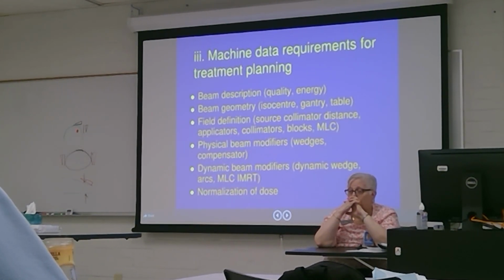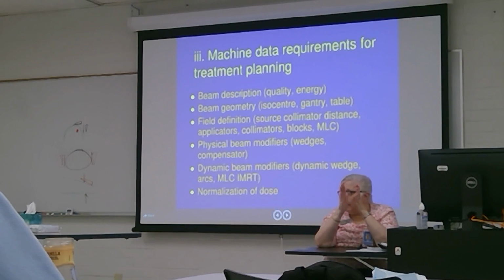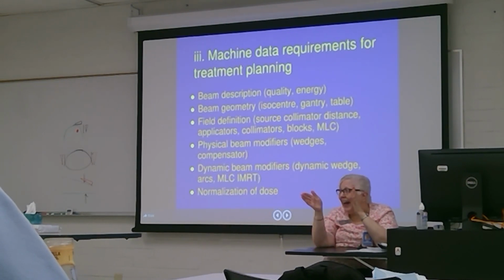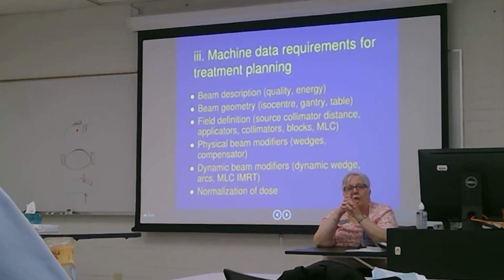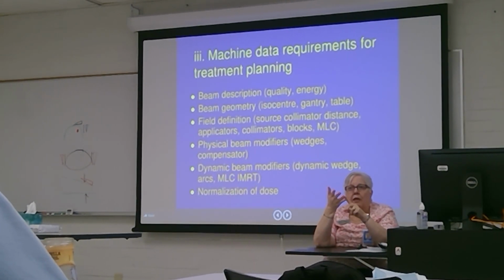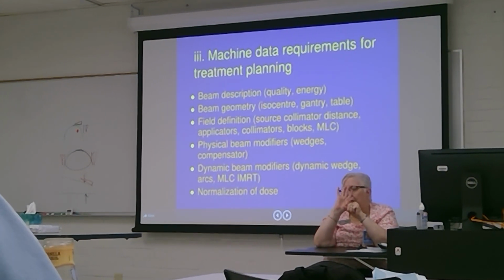I think in Gainesville on 4, it went anywhere from 4 to 20. Yeah, but in between, which electron applicators did you have? 4, 6, 10, 14, 20. Okay. And in most Varian machines, it's 6, 10, 15, 20, 25. And if you're using a 25 cone, make sure you have two of you to put it on, because it's really heavy.